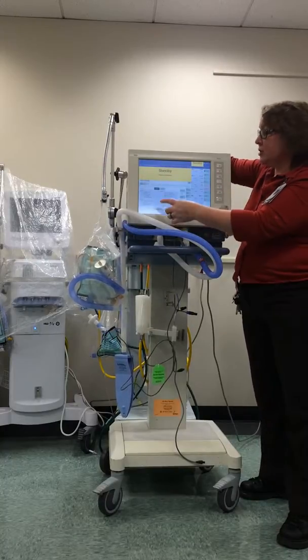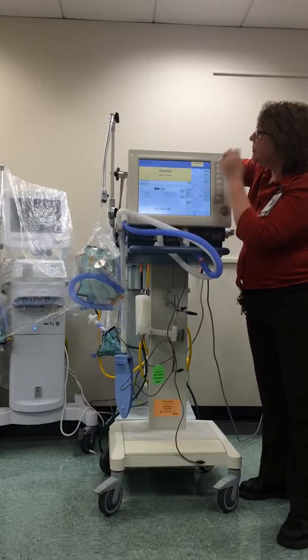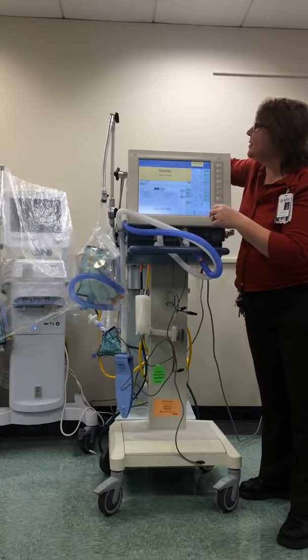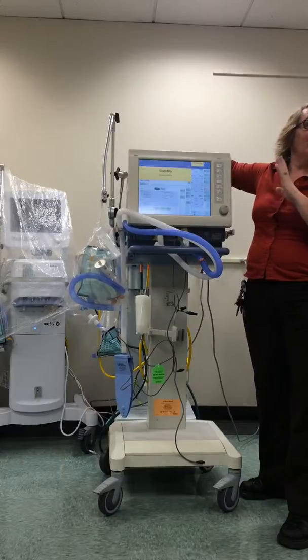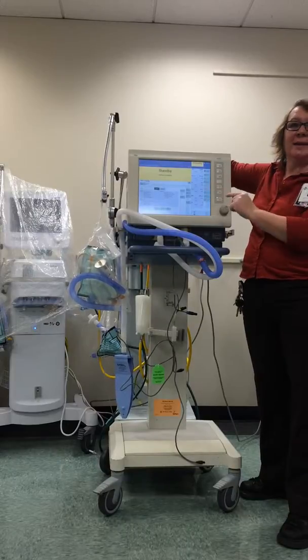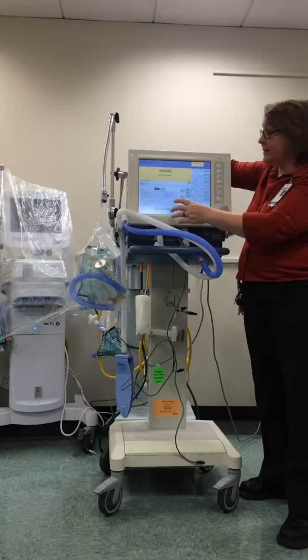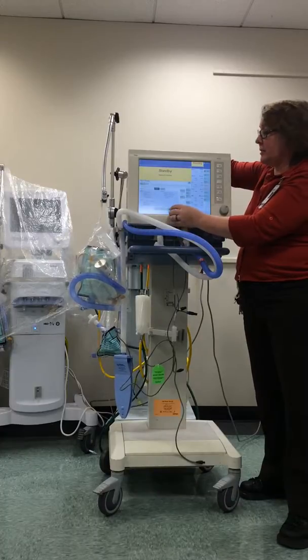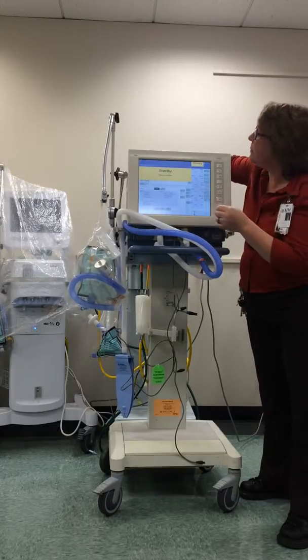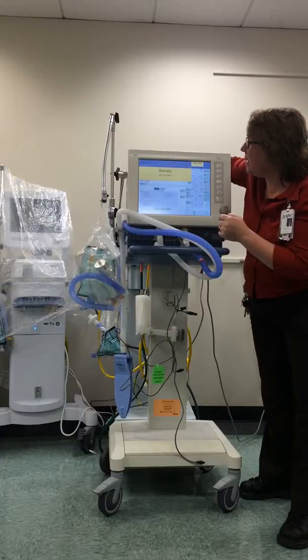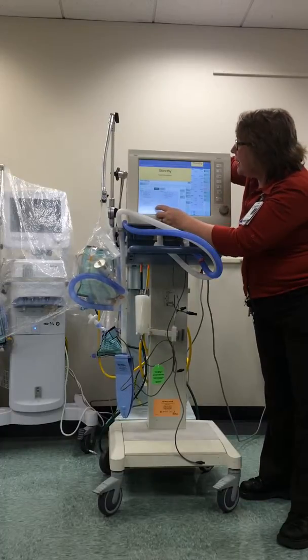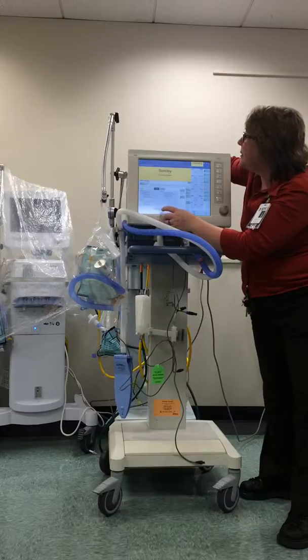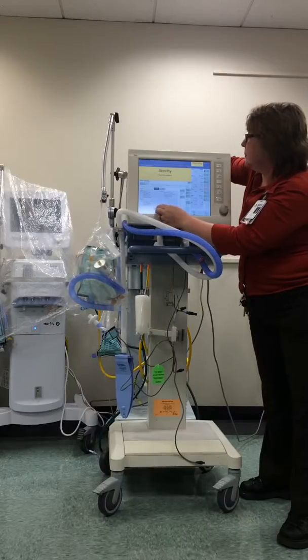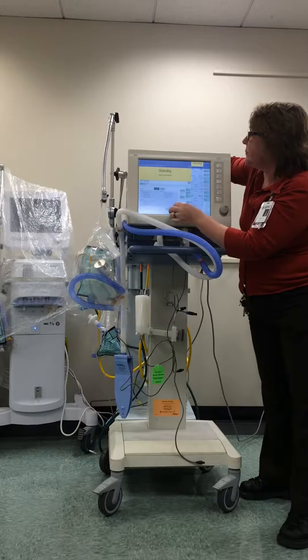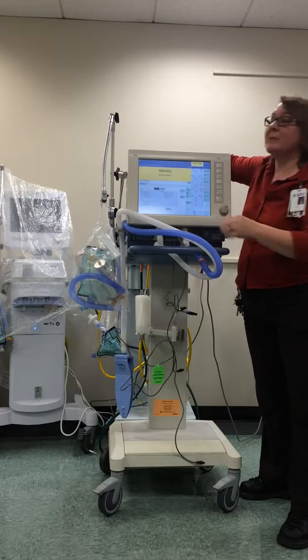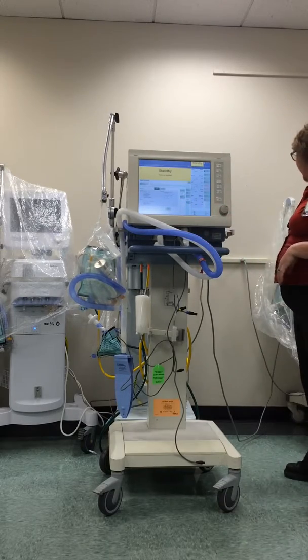So check correct position of the flow sensor, hit yes. Neo sensor placed at the Y piece. We don't have a Neo sensor, so don't hit no, hit next test. I'm going to hit next test when it says anything about a Neo flow sensor. Is HME filter ready for use? I'm just going to say yes to that one. Connect air supply, disconnect oxygen supply. So we're going to unhook the O2.